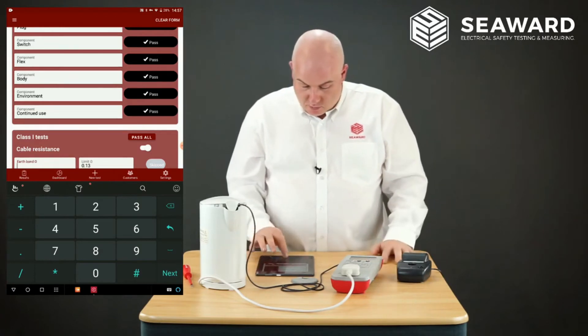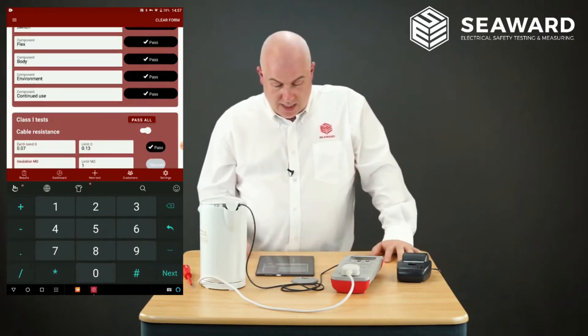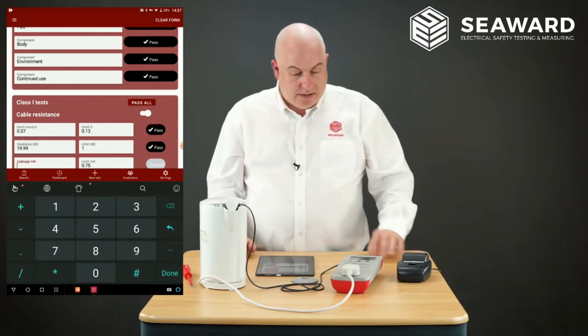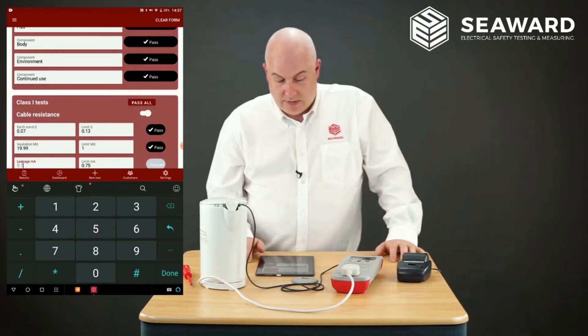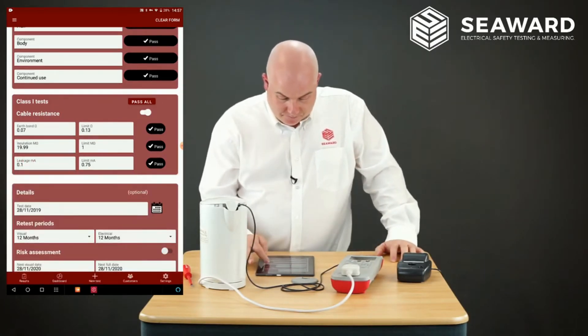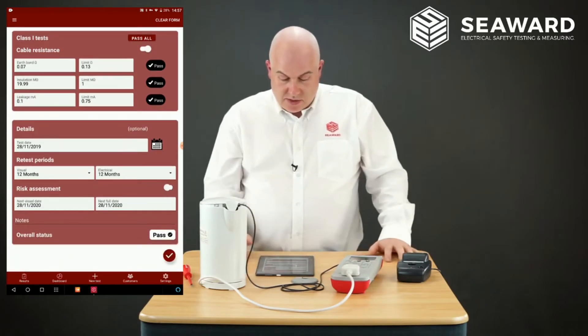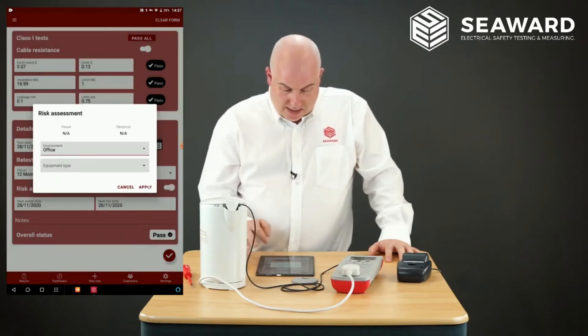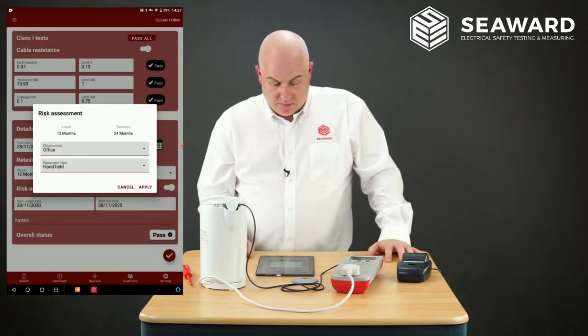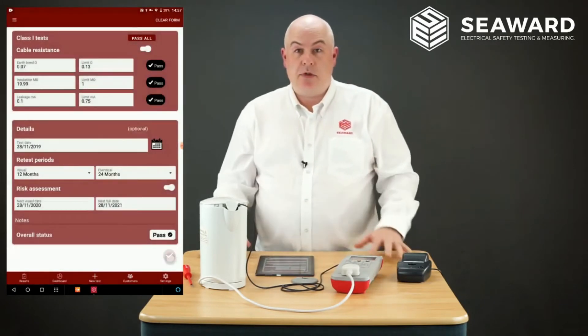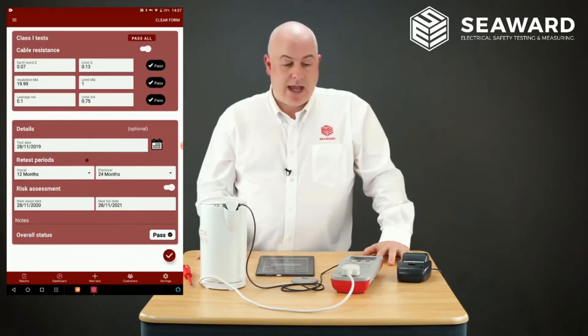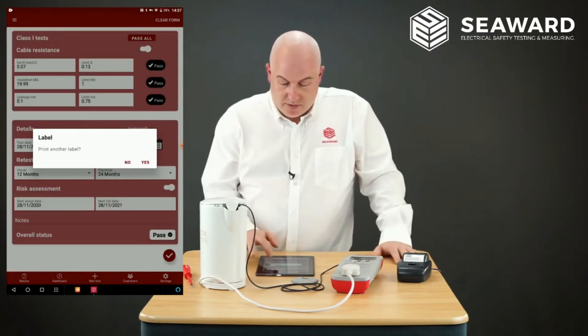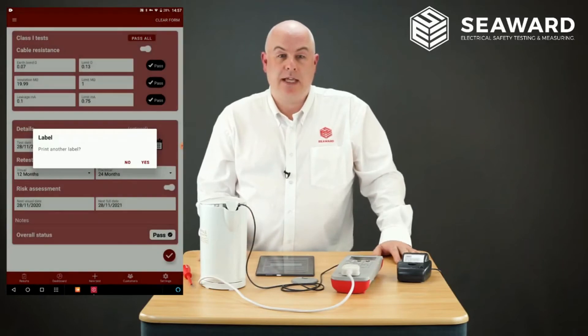Earth bond comes up as 0.07, so I record that. Insulation is 19.99 megaohms and leakage is 0.1 milliamps — I record those as well. Using the risk assessment, I fill in Office and Handheld, select both, and press Apply — that sets the retest dates accordingly. I save that as a pass, and if I want to print a label I press Yes to get the label, and Yes again if I want another one for the base.